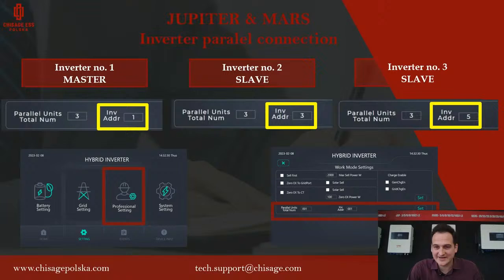And then we go to settings. So we go to professional settings, and we have to fill in these settings. For three inverters, we go with parallel unit total number 3. In all three inverters it will be the same number, so it will be 3. And for inverter address, as I said, each inverter takes 2 addresses. So master will be 1, then slave number 2 will be inverter address 3, and then 5. If we connect another one, it will be 7, etc. So we have to fill in this information too, and always inverter address number 1 is the master inverter.